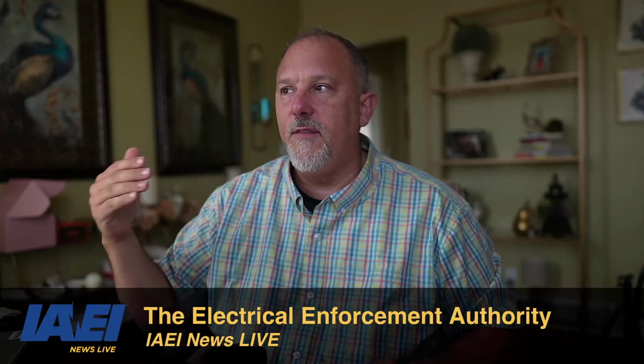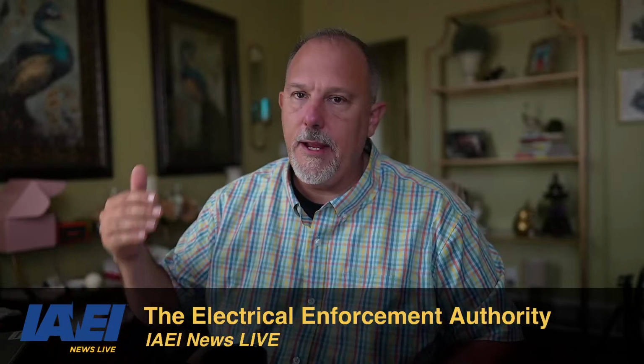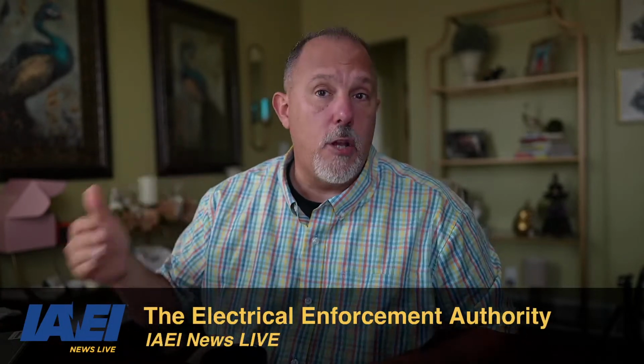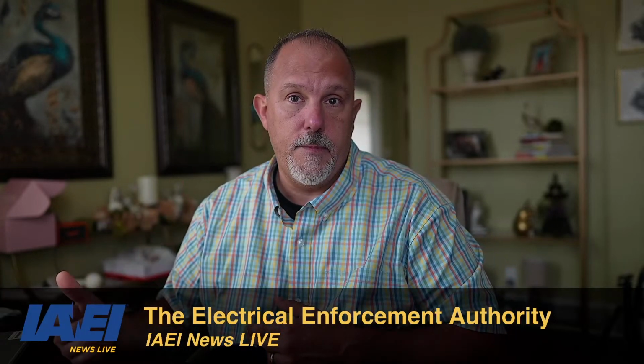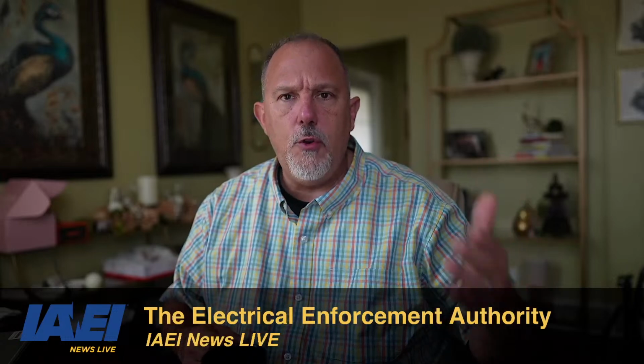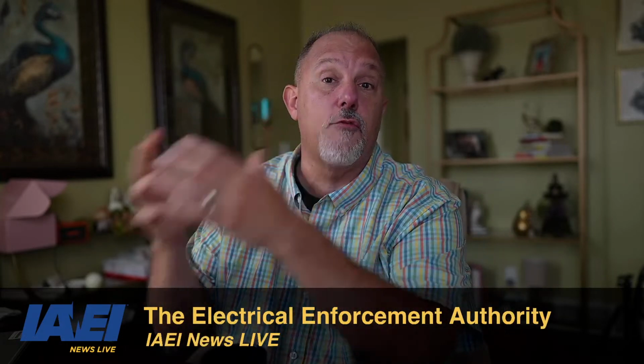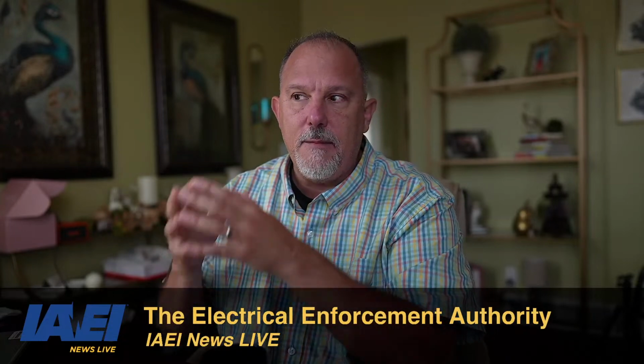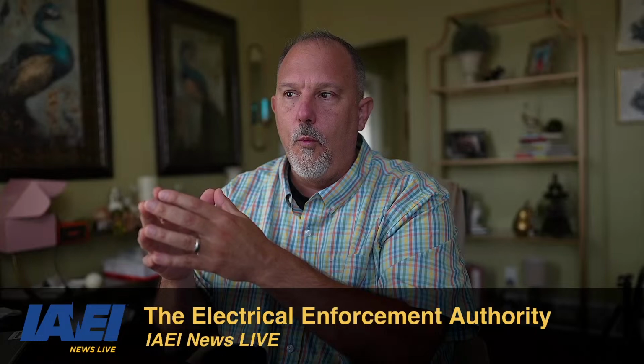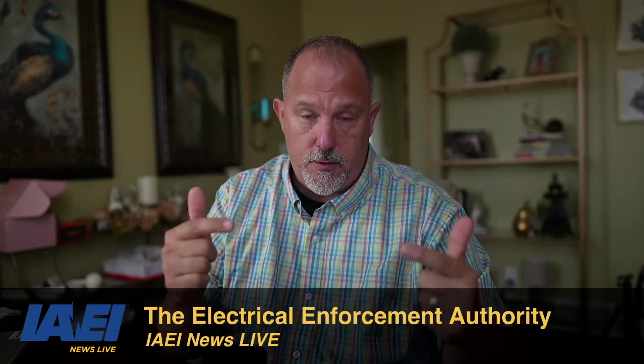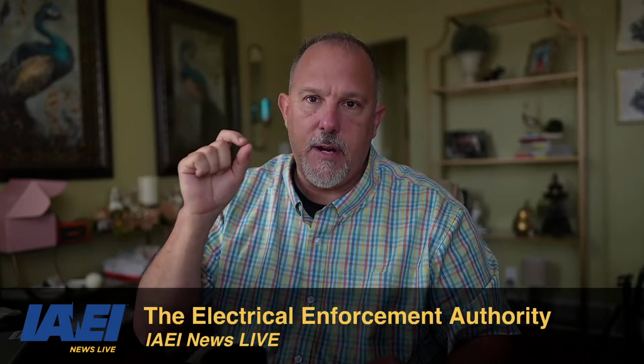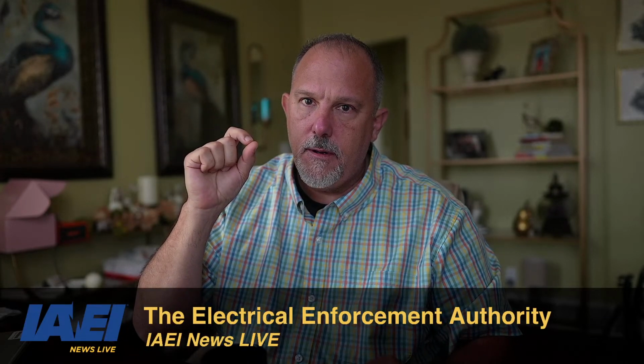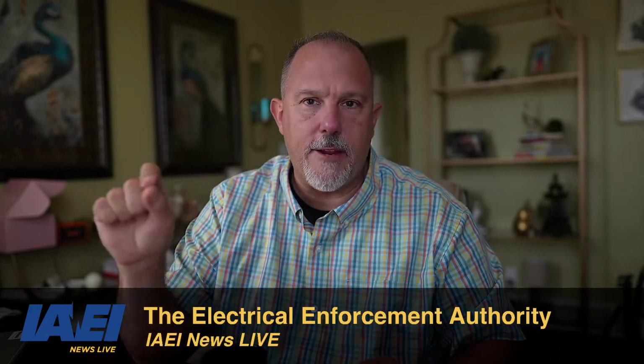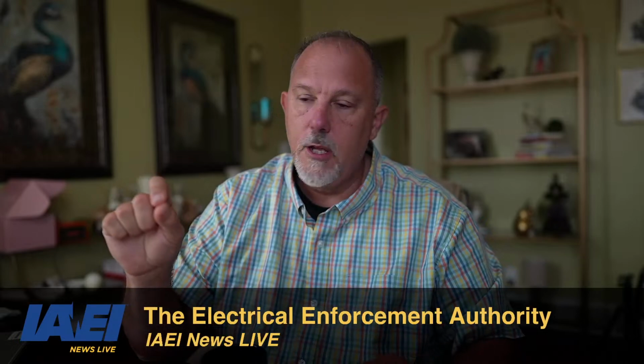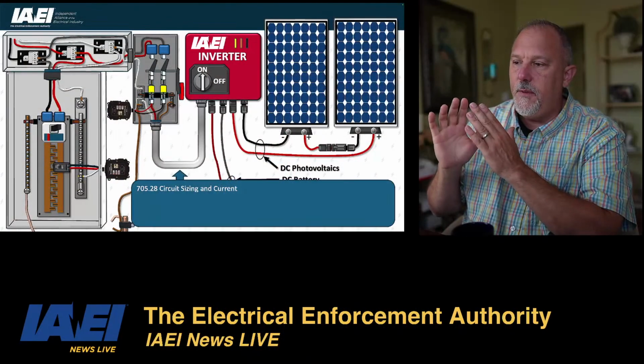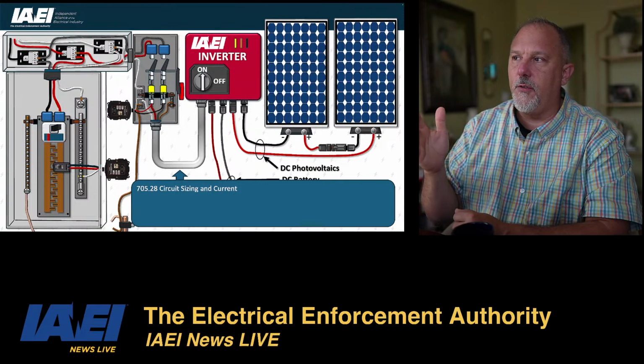When you are dealing with inverters and you're dealing with photovoltaics, wind, energy storage systems, those aren't loads, those are power sources. So when I think about the amount of current passing through a conductor, I can't think about that in regard to what I normally think about, which is loads. I have to focus my calculation, I have to focus my energy around power sources. So when I'm thinking of these conductors that are coming from an inverter, they're not loads.